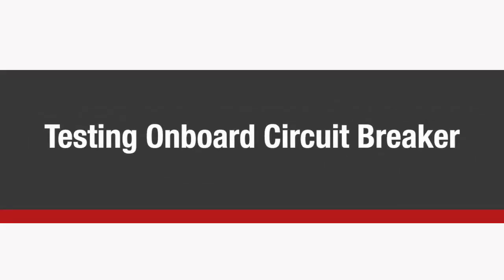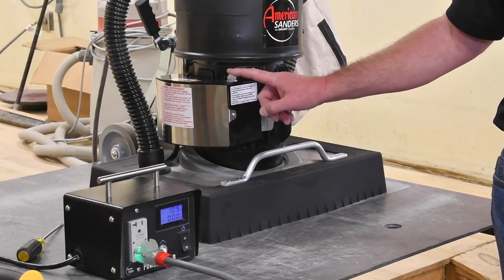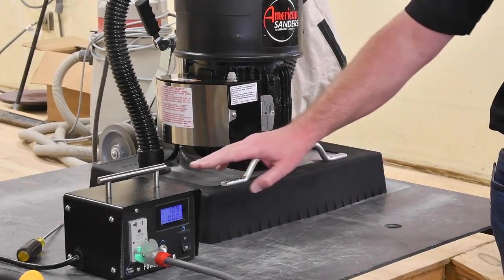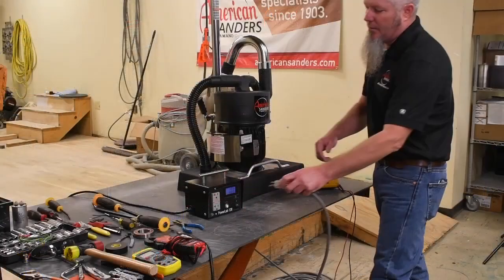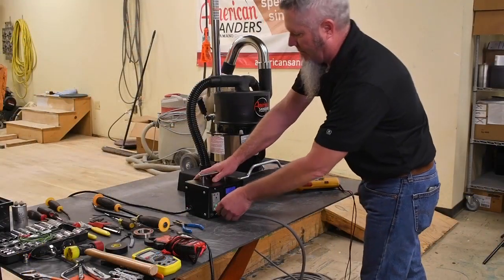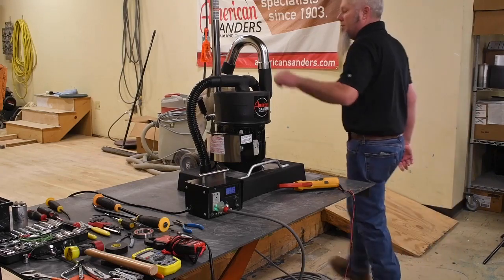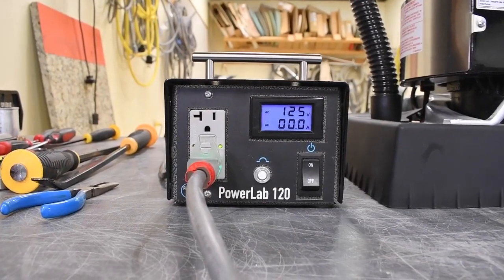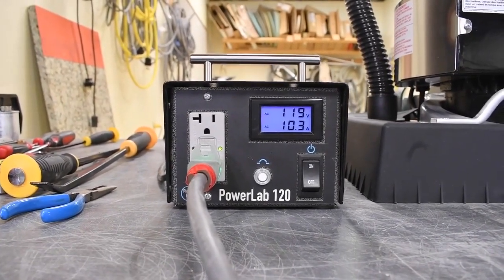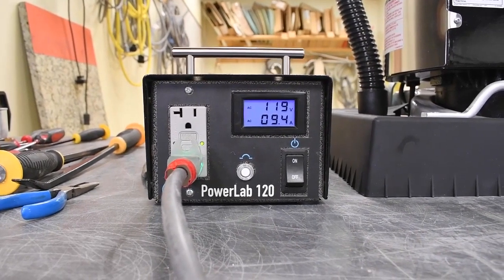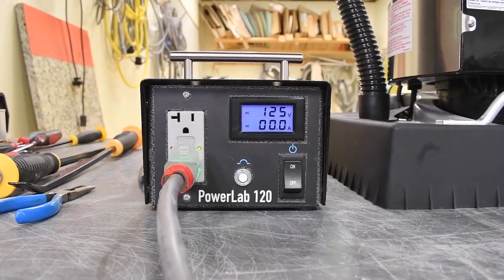Testing the machine circuit breaker. The PowerLab 120 is a useful tool to diagnose a machine circuit breaker. Plug the machine into the PowerLab 120 and safely run the machine. With a 125 line voltage, if the machine is drawing less than 15 amps and the breaker trips, that indicates a bad breaker that needs to be replaced.